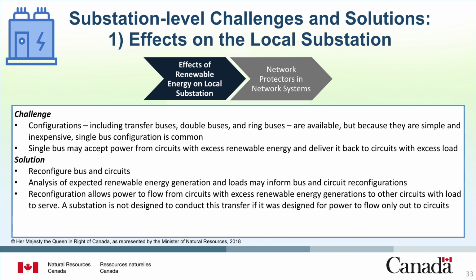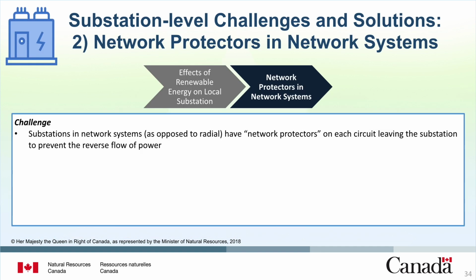The intent of this reconfiguration would be to allow power to flow from circuits with excess renewable energy generation to other circuits with load to serve. Now let's discuss the other challenge at the substation level: network protectors. Substations in network systems, rather than purely radial, have network protectors on each circuit leaving the substation to prevent a reverse flow of power. Integrating renewable energy into a network power system may require special controls to prevent the renewable energy power from ever exceeding the load and potentially tripping the network protectors.